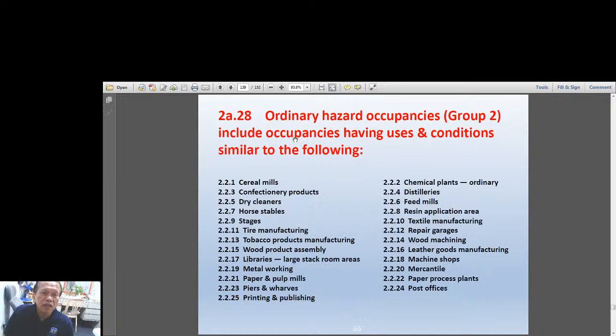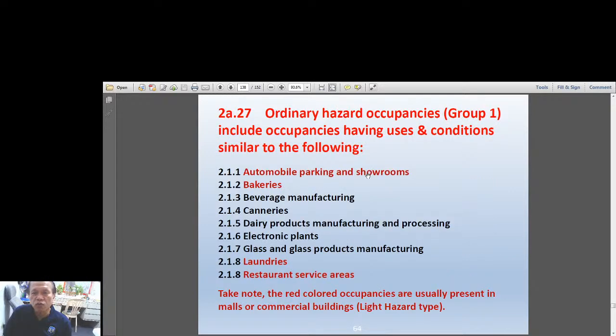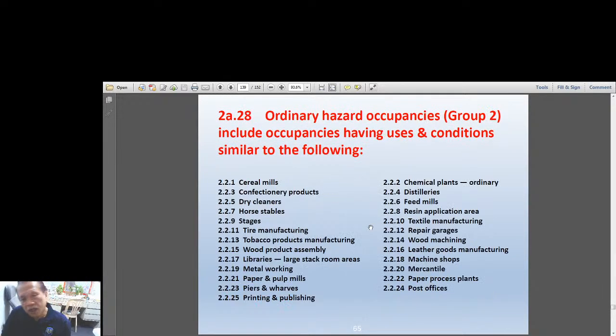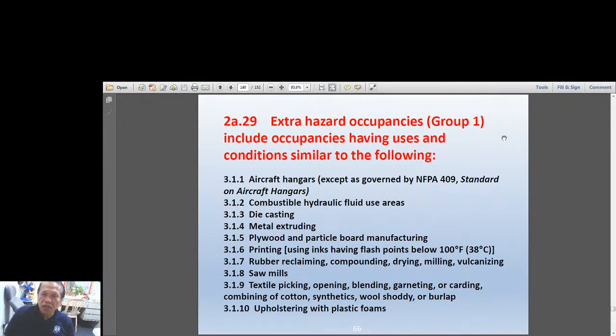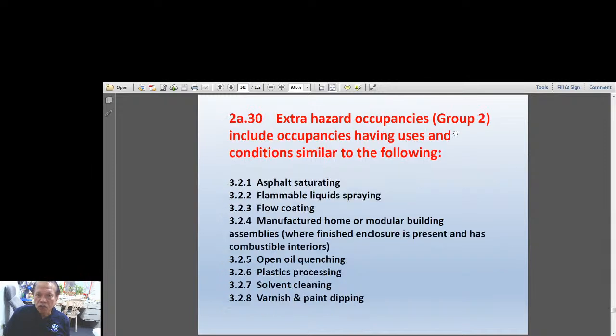Okay, then here is the ordinary hazard group 2, because the first one is ordinary hazard group 1. This one, ordinary hazard group 2, and then extra hazard group 1, mostly industrial, and the extra hazard group 2 there, also industrial.